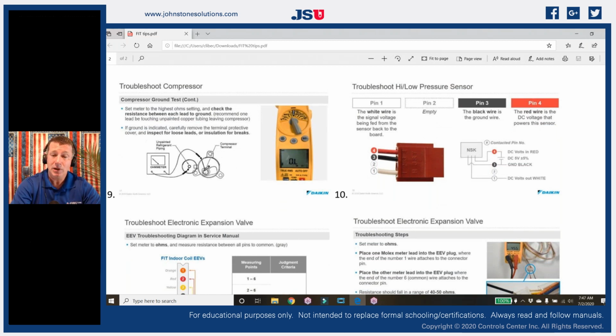Now, when we start talking about the sensors and the temperature or pressure transducers that are going into these pieces of equipment, we just need to understand what they are. It'll help you see what's going on inside of an inverter. Remember, this is built for our Daikin equipment, but it's really good for all inverter technology. It doesn't even matter the size of the piece of equipment. It's using the same principles.